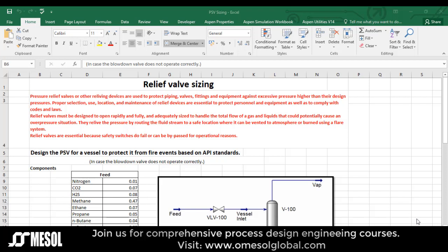Relief valves must be designed to open rapidly and fully, and adequately sized to handle the total flow of gas and liquids that could potentially cause an over-pressure situation. They relieve the pressure by routing the fluid stream to a safe location where it can be vented to atmosphere or burnt using a flare system.